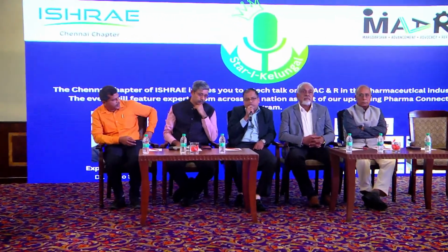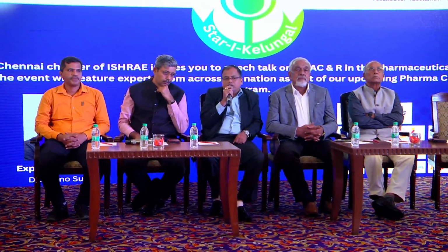Whatever standards we are talking about, when we talk about particle concentration and classification, that is ISO 14644 part 1, and most of the tests we have already covered. To start with the basic tests: air velocity, air volume, particle count, and along with the particle count, we have a recovery test and compressed air validation test. There are many things we can do. I don't think there is anything apart from the standard that is called advanced. Is that right, sir?